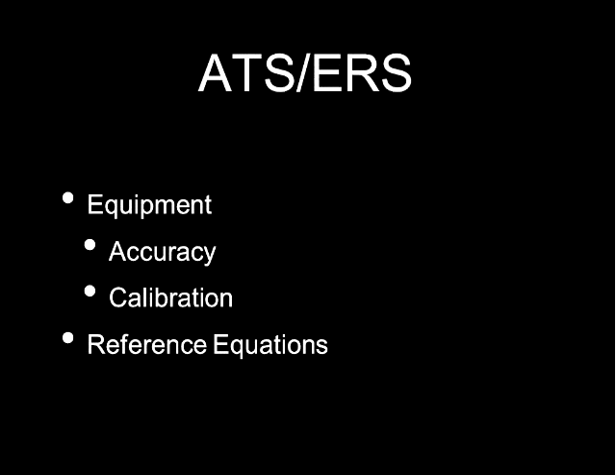The equipment standards were also included in here. Again, they agreed with the plus or minus 3% accuracy for devices, and they both said that pulmonary function labs should be calibrated using manufacturers' recommendations. Unfortunately, a lot of the manufacturers of simple spirometry devices are now saying it's not necessary to ever calibrate their devices.